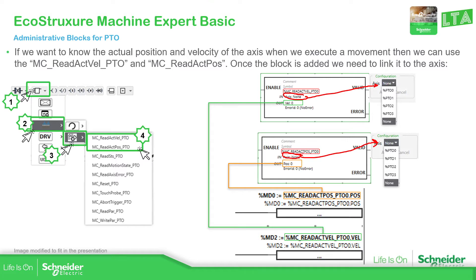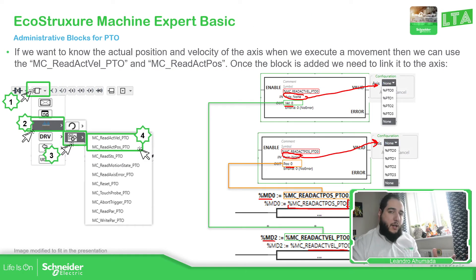We can read the actual position and actual velocity using the block when you are online. But if you want to share this information to an HMI, you need to use the instance of the PTO and then the number you have — dot position or dot velocity from the readActualVelocity — and move that value to a %md variable so you can use it in an HMI.